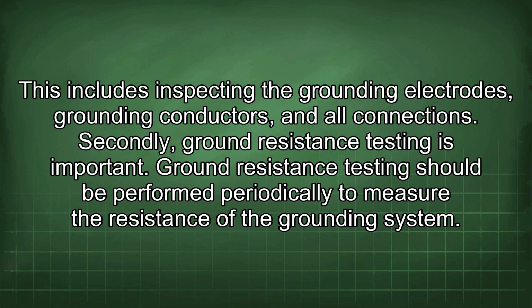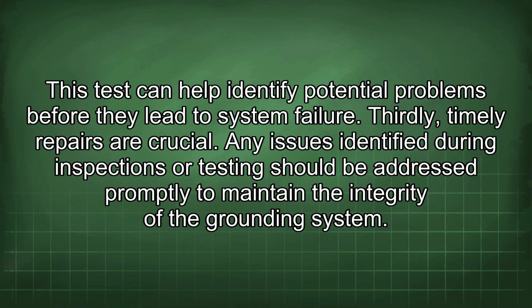Secondly, ground resistance testing is important. Ground resistance testing should be performed periodically to measure the resistance of the grounding system. This test can help identify potential problems before they lead to system failure. Thirdly, timely repairs are crucial. Any issues identified during inspections or testing should be addressed promptly to maintain the integrity of the grounding system.